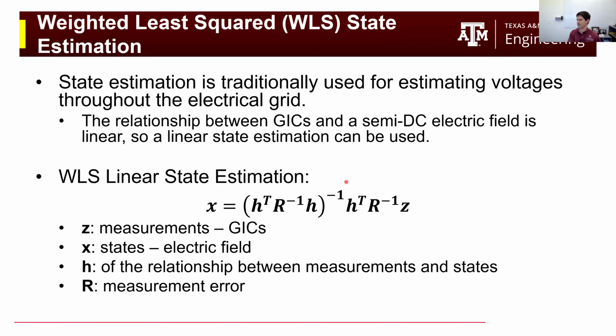But in this case, we're doing it a little bit differently. Instead of a traditional state estimation where P and Q are your measurements and voltage phase angle is your state, it's typically an overdetermined system. You typically have more P and Q measurements than you need, so you can do things like bad data detection or rejection of measurement error, etcetera.